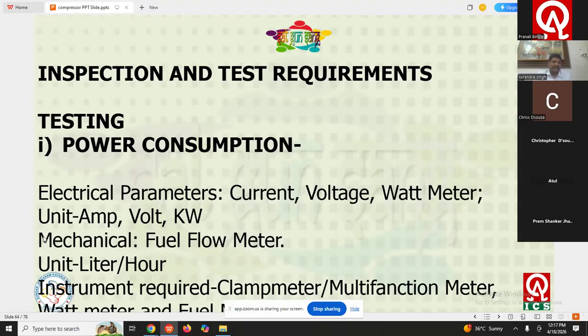If the driver source is from mechanical side, then we need to check the fuel consumption through the fuel flow meter, and then the unit is the liter per hour, which is the fuel consumption unit. The instrument required for the above measurement is clamp meter, multifunction meter, watt meter, and the fuel meter.